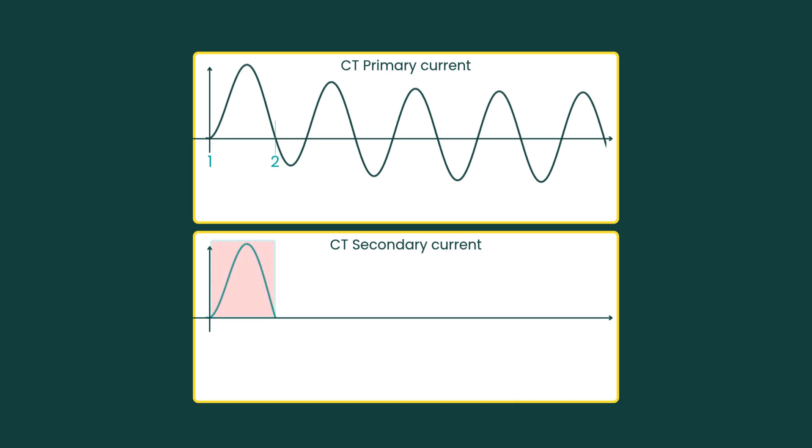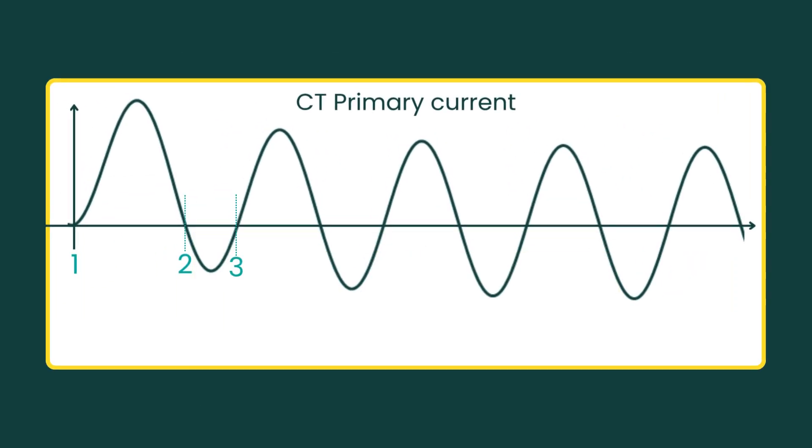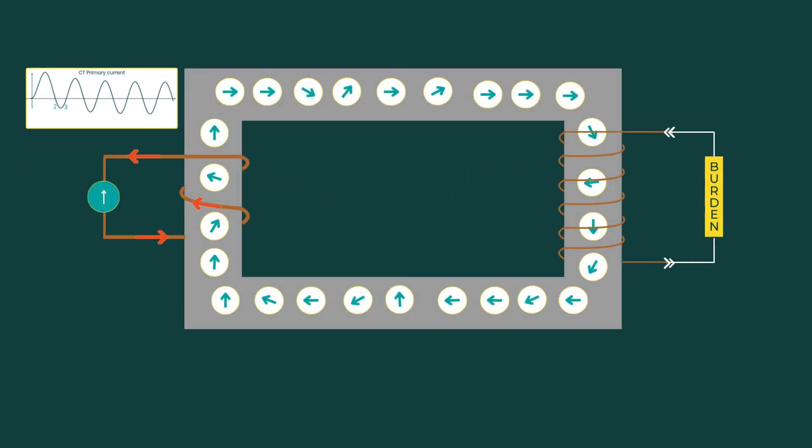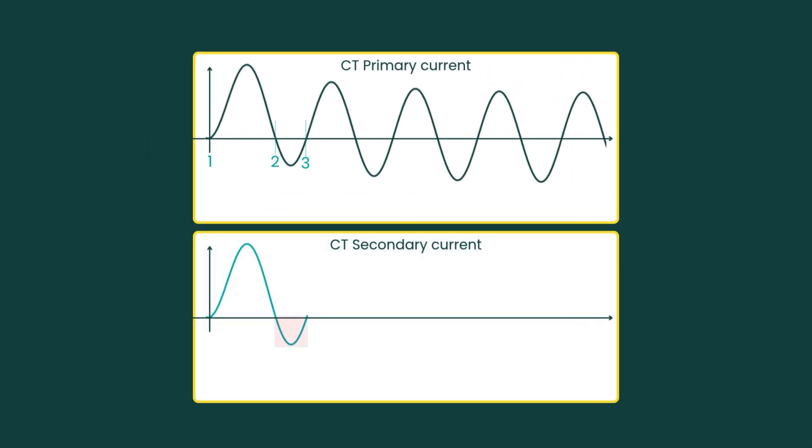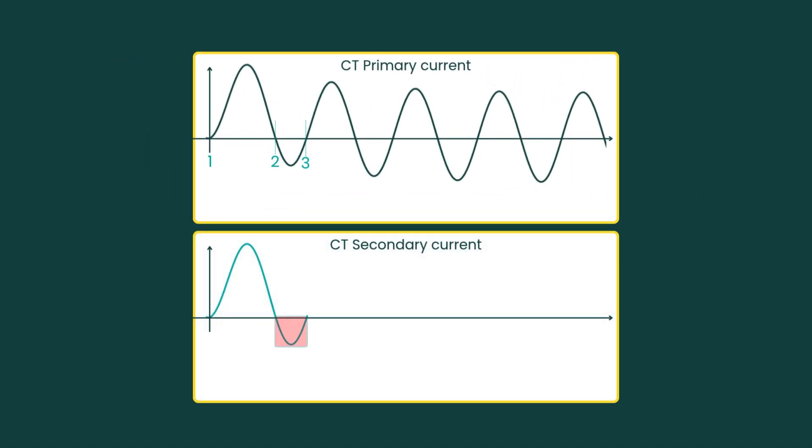Then comes the first negative half cycle, from point 2 to point 3. The current goes negative, but because of the DC offset, the negative half cycle is short and not very strong. Only a few dipoles manage to reverse before the current turns positive again. The flux is changing, so the CT works as expected; the secondary current follows the primary current, scaled by the CT ratio.